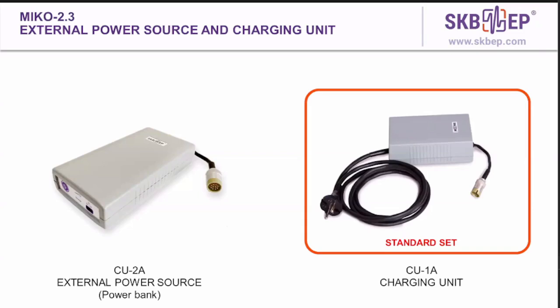Well, here we have two options of power supply to this instrument. Charging unit CU1A for charging the built-in condenser battery during operation on electrical equipment. And another is external power unit or power bank to provide the autonomy operation of the device without connection to the mains. So micro-ohmmeter mode can perform 20 measurements at test current of 1000 ampere. Milliohmmeter mode can work during 3 to 4 minutes.